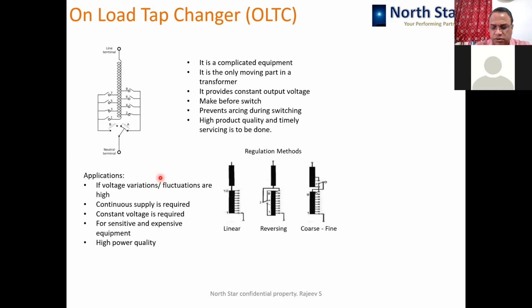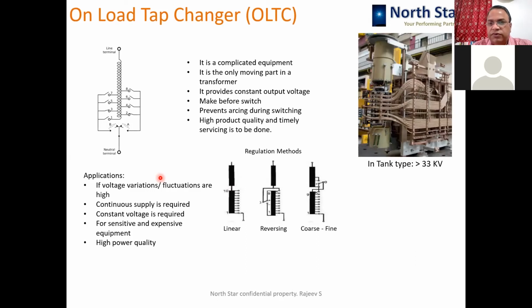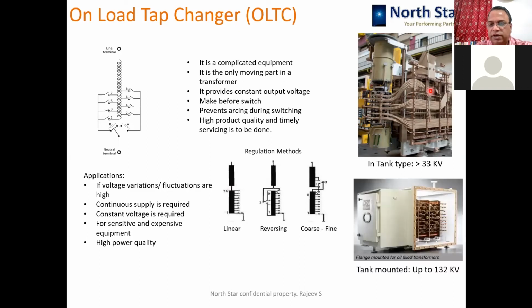So it is used where you want continuous supply, or there is a very high level of voltage fluctuation, or you have a very sensitive system where you cannot afford voltage fluctuations and you require higher power quality. So this is the OLTC looked at from inside. This is the OLTC which is being put to the transformer, connected to the transformer. Okay, it is an in-tank type, and these in-tank type OLTCs are normally used for voltages more than 33 kV. Now, further developments have happened, and these OLTCs are available at lower voltages also, 11 kV and lower, and you can also use the in-tank type of OLTC, which is very compact and can be put in the tank mounted on the cover. So you can use those OLTCs for in-tank also. And there are tank mounted OLTCs which are available up to 132 kV voltage classes.